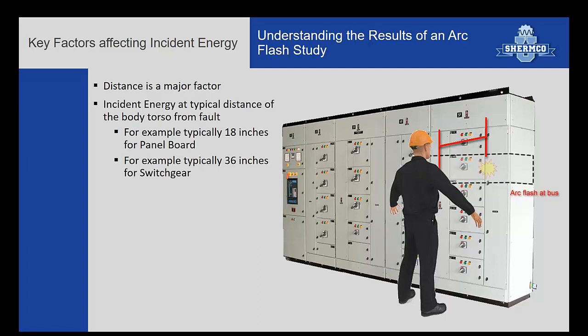You typically see, I have some examples here, like on the arc flash label, 18 inches, where the incident energy was calculated. And that 18 inches, we're going to go through where that comes from, but typically it's from where the event is occurring to the body of the worker. Hands and arms may be closer, so you have to take that into account too. When these working distances are selected, they're typically selected for how far away the worker would be from the device.